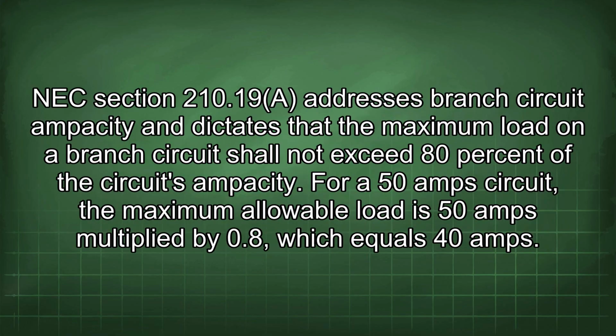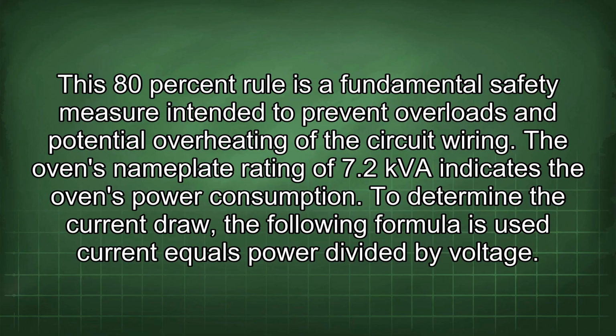NEC Section 210.19 addresses branch circuit ampacity and dictates that the maximum load on a branch circuit shall not exceed 80% of the circuit's ampacity. For a 50 amp circuit, the maximum allowable load is 50 amps multiplied by 0.8, which equals 40 amps. This 80% rule is a fundamental safety measure intended to prevent overloads and potential overheating of the circuit wiring.